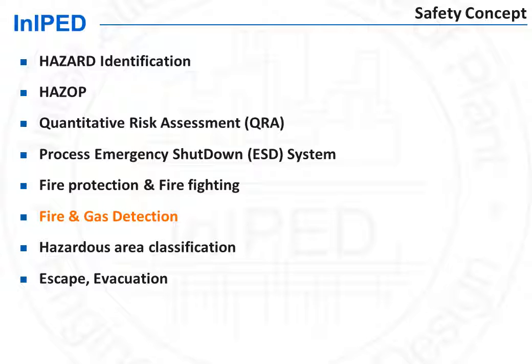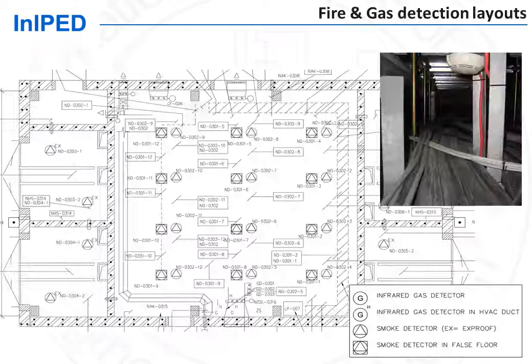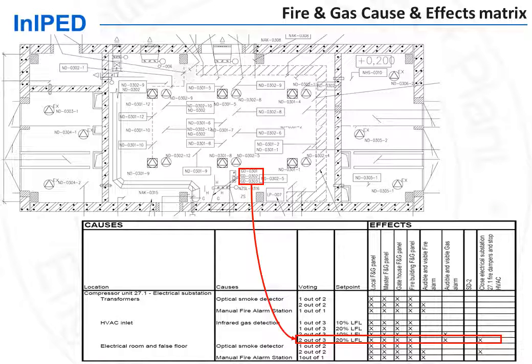Safety designs the fire and gas detection system. The fire and gas detection system gives alarm and executes automatic actions such as process shutdown, shutdown of building ventilation, and release of firefighting agents upon fire or gas detection. Detectors are provided throughout the process areas and within buildings. The actions initiated upon detection are defined by safety on the cause and effect diagrams. For instance, gas detection in the inlet ventilation ducts of a building is shown to stop the ventilation.